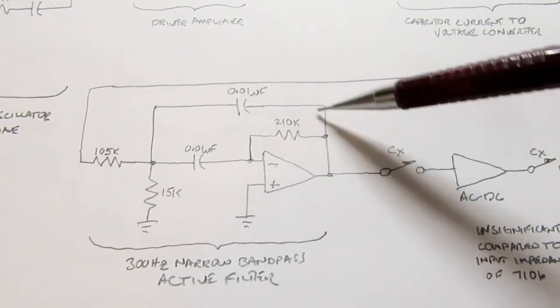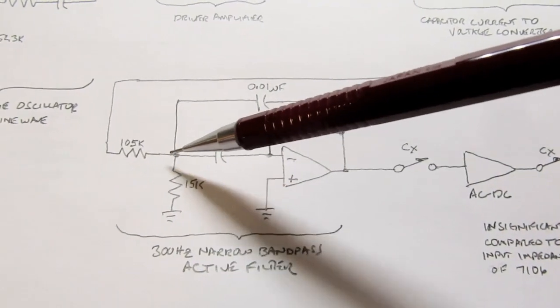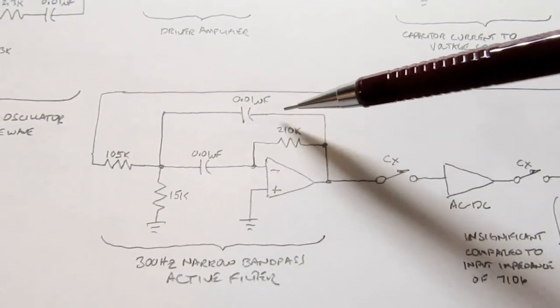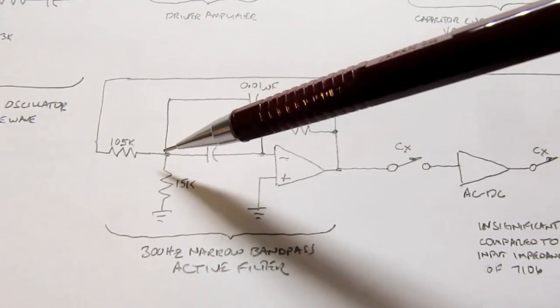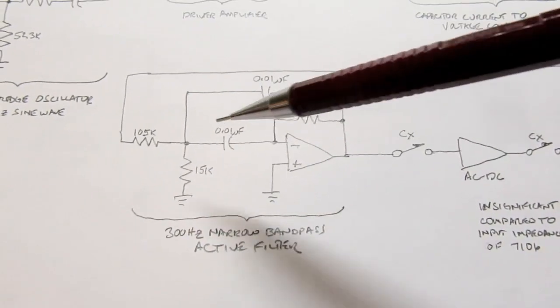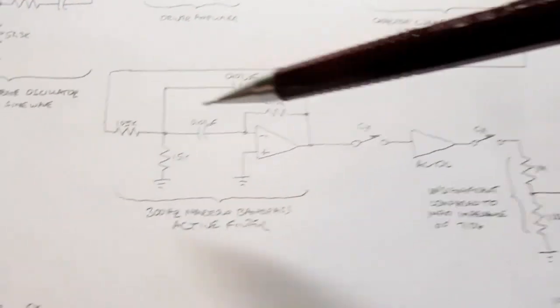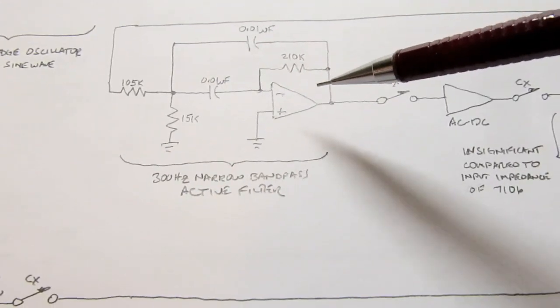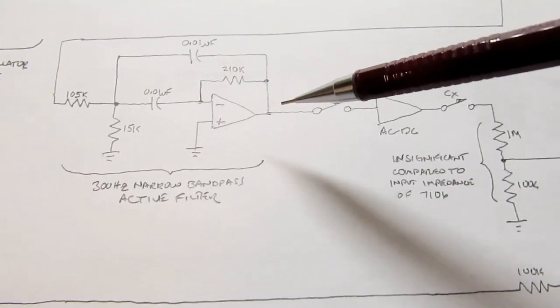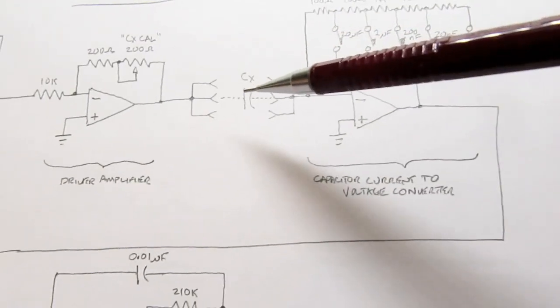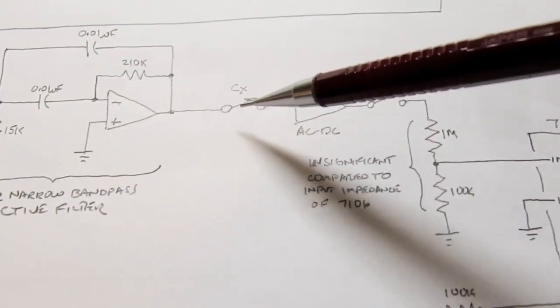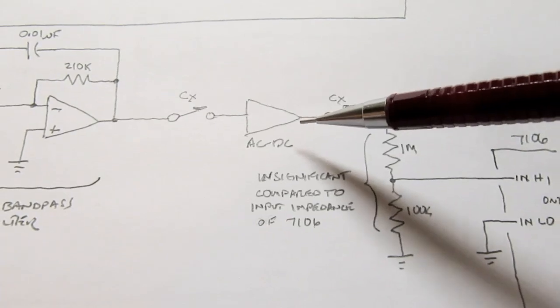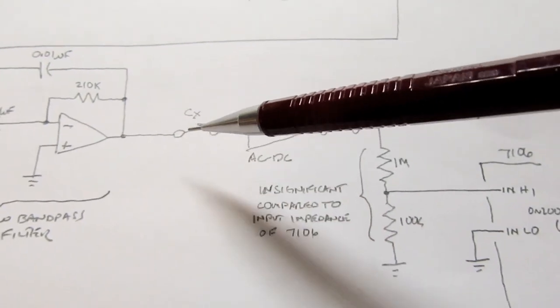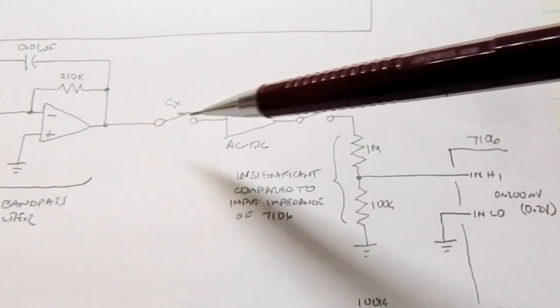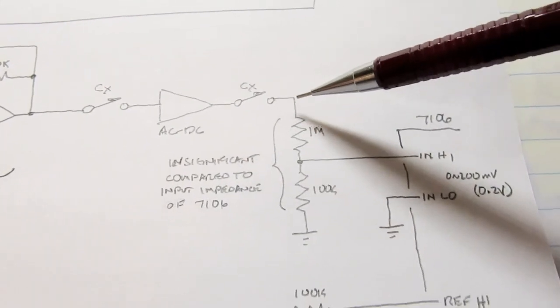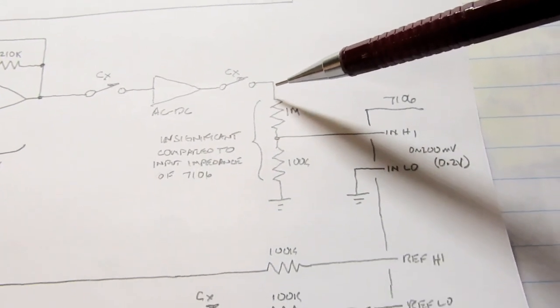You've got a resistive feedback path with a capacitor to the input signal, and you've got a capacitive feedback path with a resistor to ground, and then you're feeding it with this signal, and basically what comes out of here is strictly the 300 hertz signal at an amplitude that's proportional to the capacitance. And you run it into that AC-DC converter we talked about already, and it takes that 300 hertz signal and converts it to a DC voltage that's proportional to the capacitance.